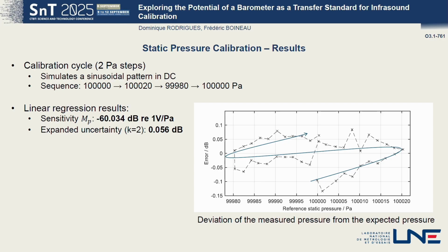So normally you have the output voltage as a function of the input pressure, but this figure here shows the measurement bias, which is the deviation between the measured pressure after calibration and the reference pressure. What's interesting here is that when following the calibration path, we can see a hysteresis effect, but to be completely honest, at this stage of the study, it was not possible to conclude definitively if it's an effect of the sensor itself or of the calibration procedure. So the question stays open.